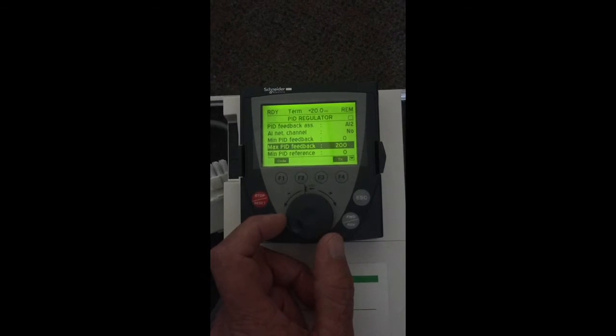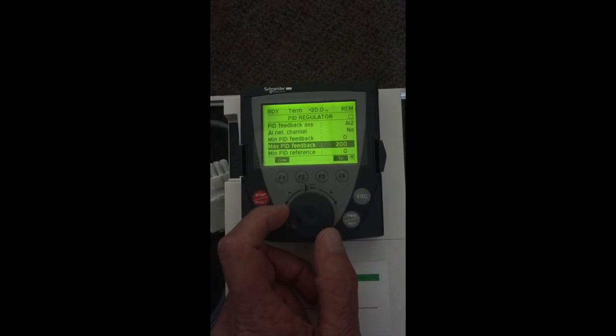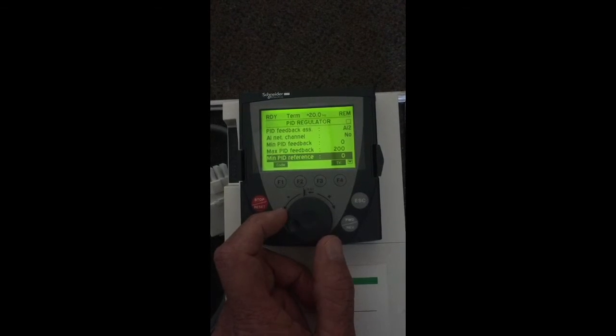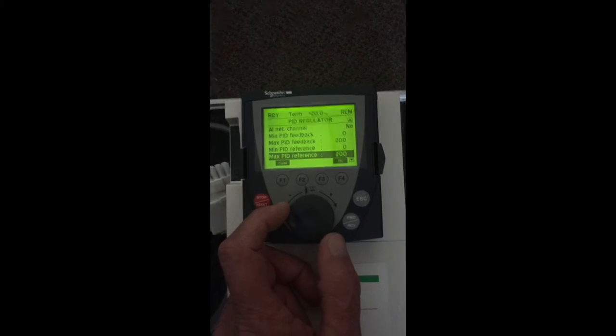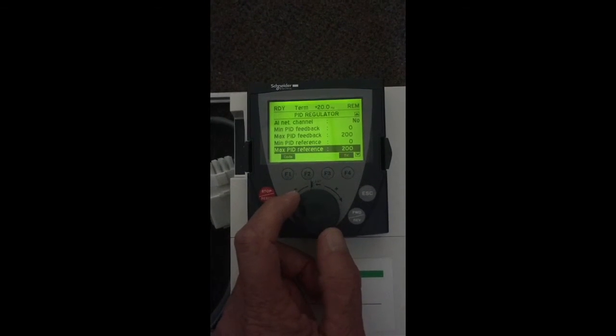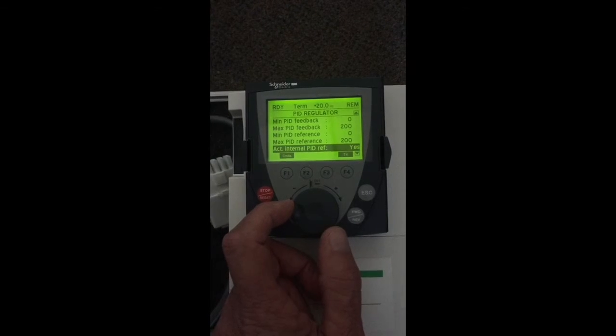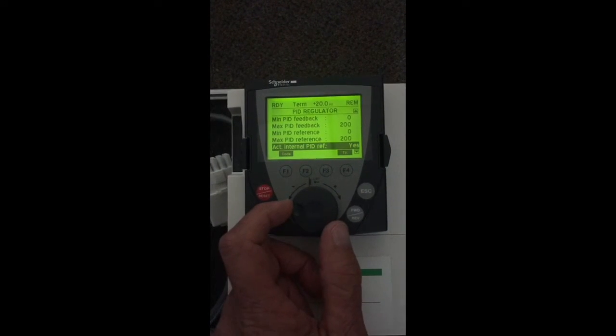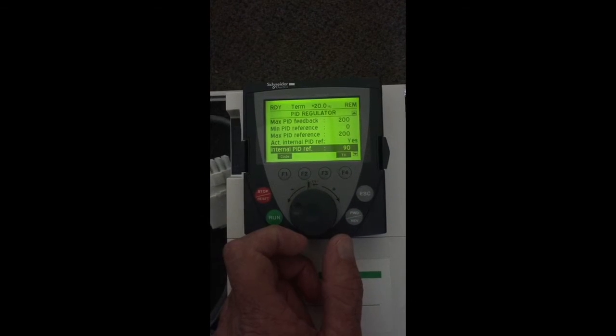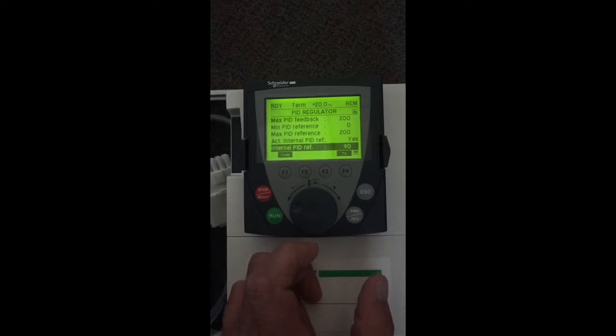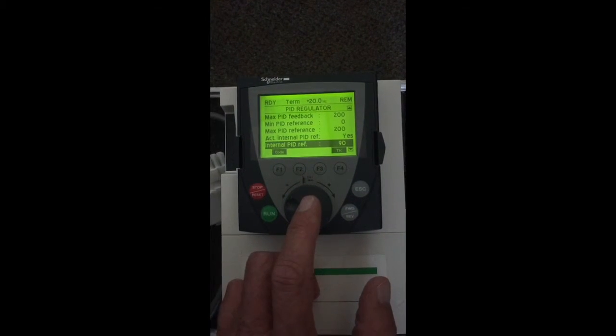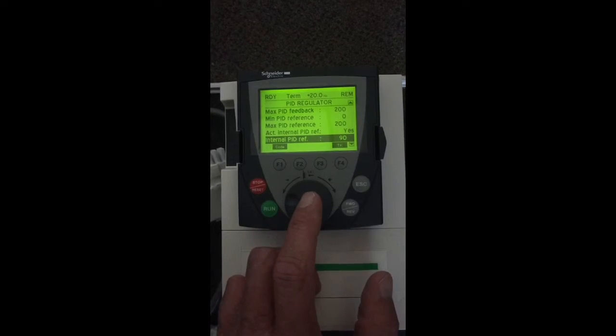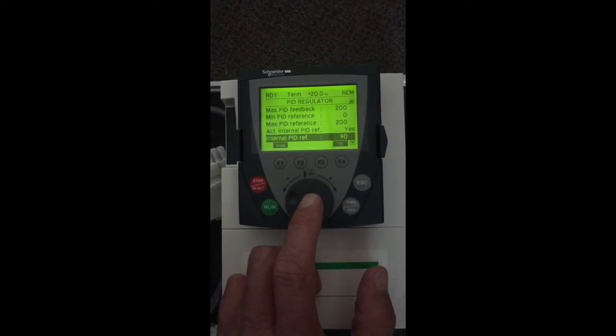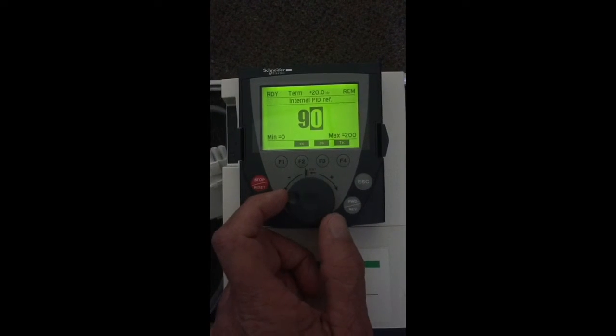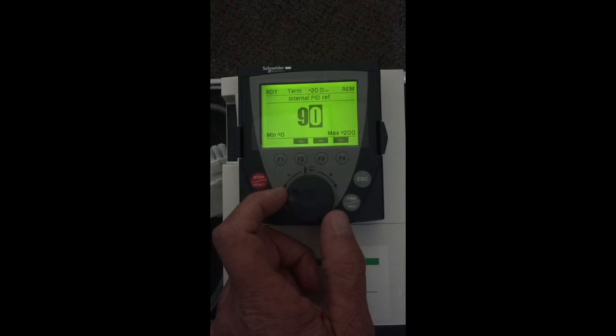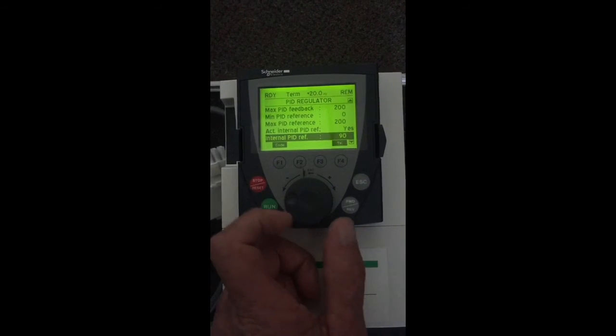I will set both of these parameters to whatever transmitter I have. Minimum PID reference scale, these will be set to the 0 and 200. Maximum PID reference. Internal PID reference is set to yes. Internal PID reference is your temperature that you want to maintain for the drive. So I'm going to be in between 0 and 200. I'm setting this for 90 degrees, fully adjustable. This is where you can make your change for your temperature. I'll enter that information.